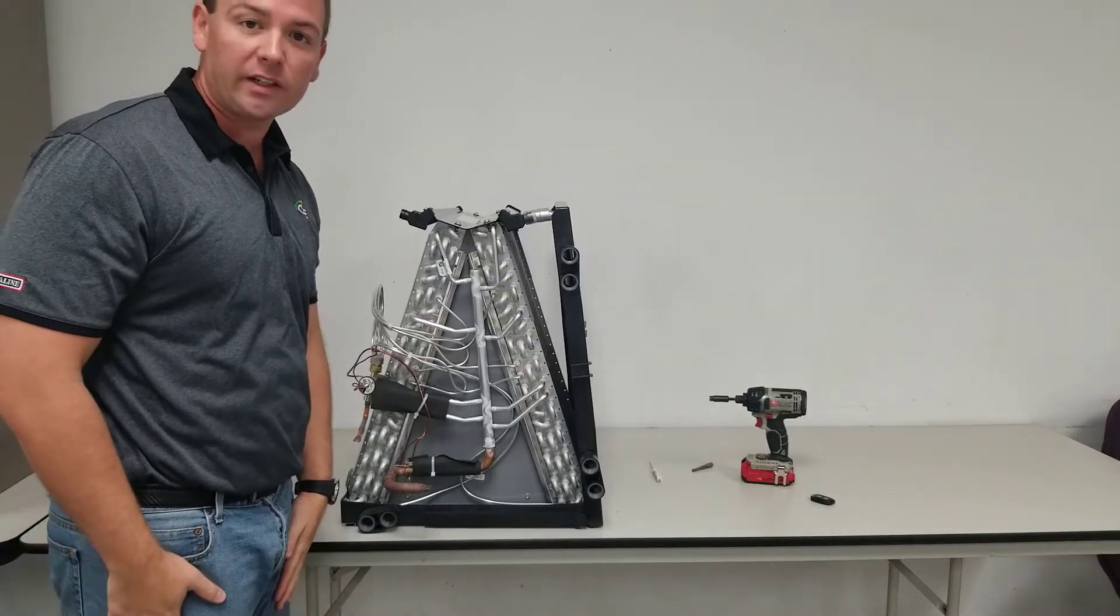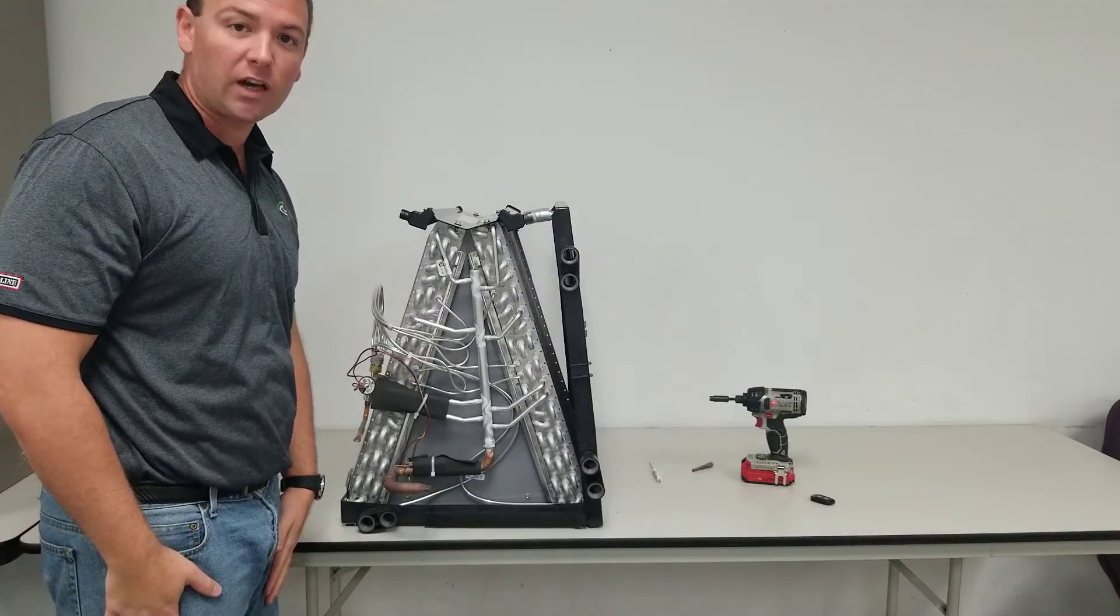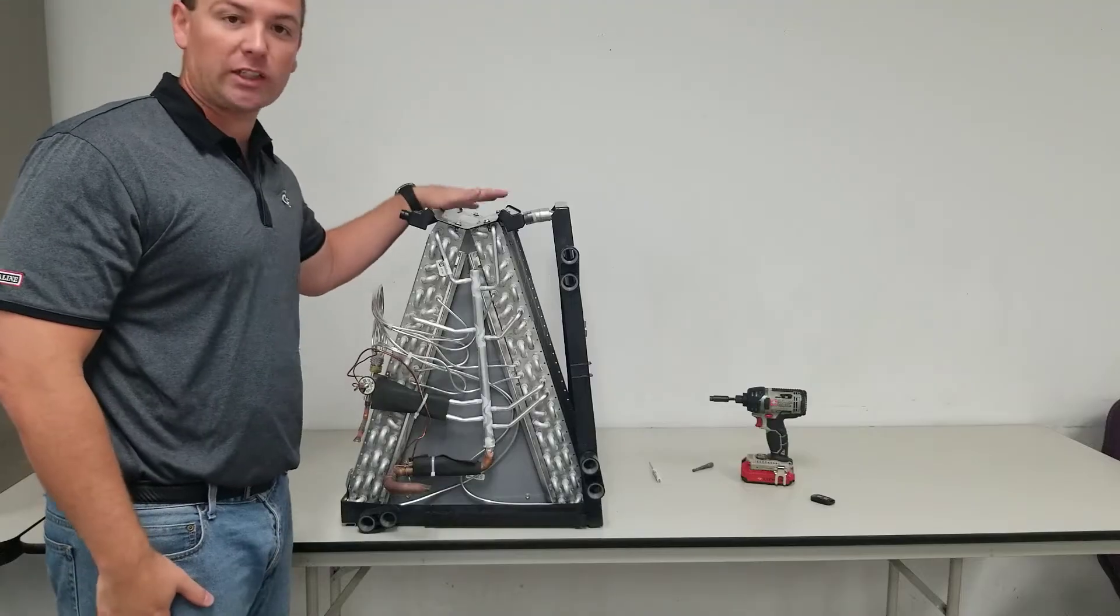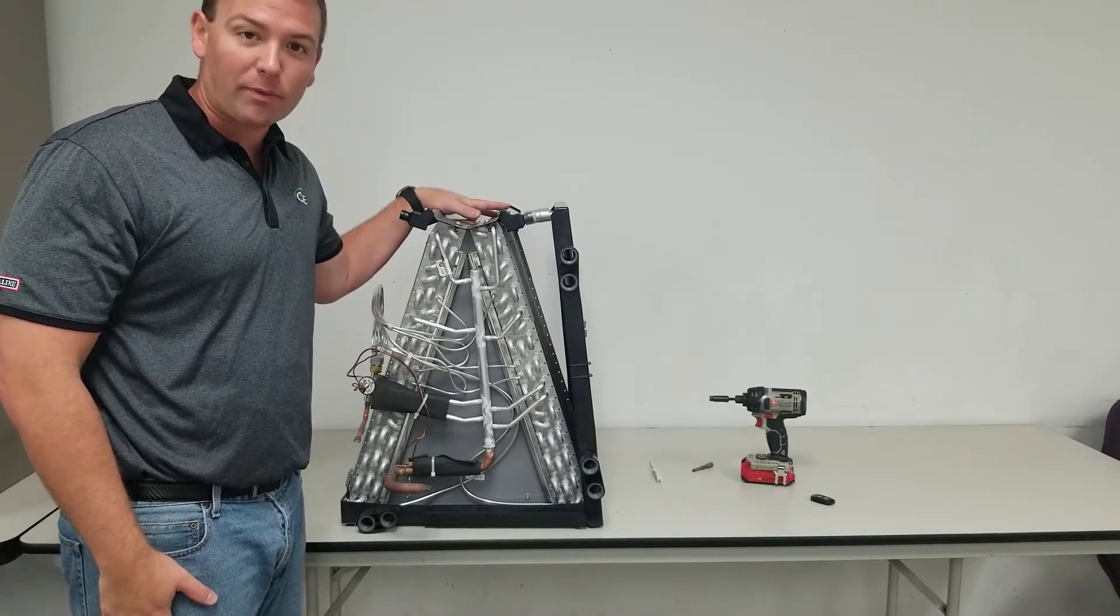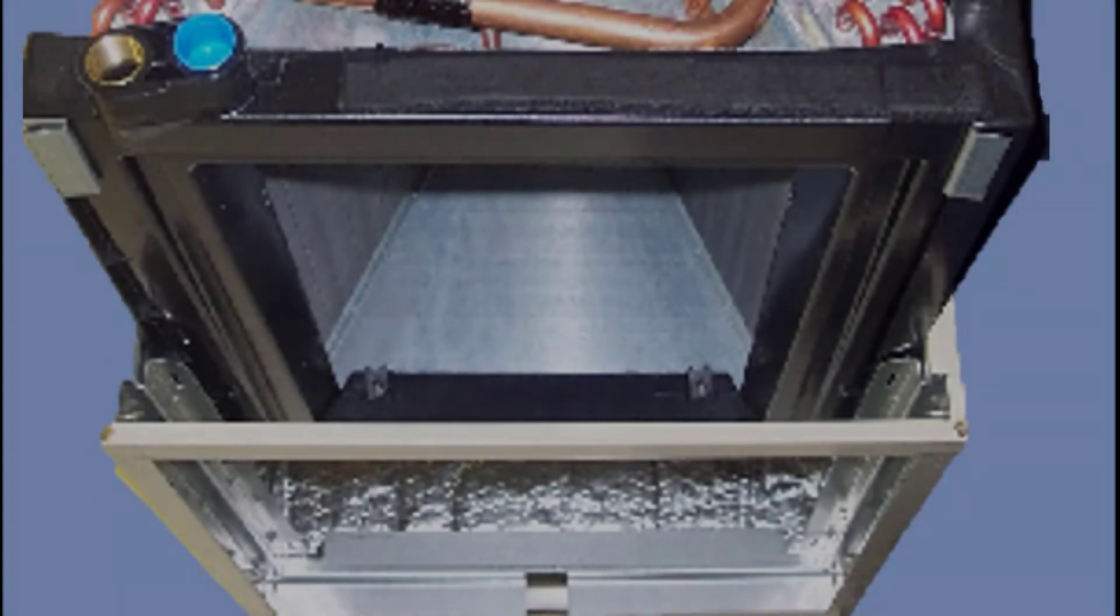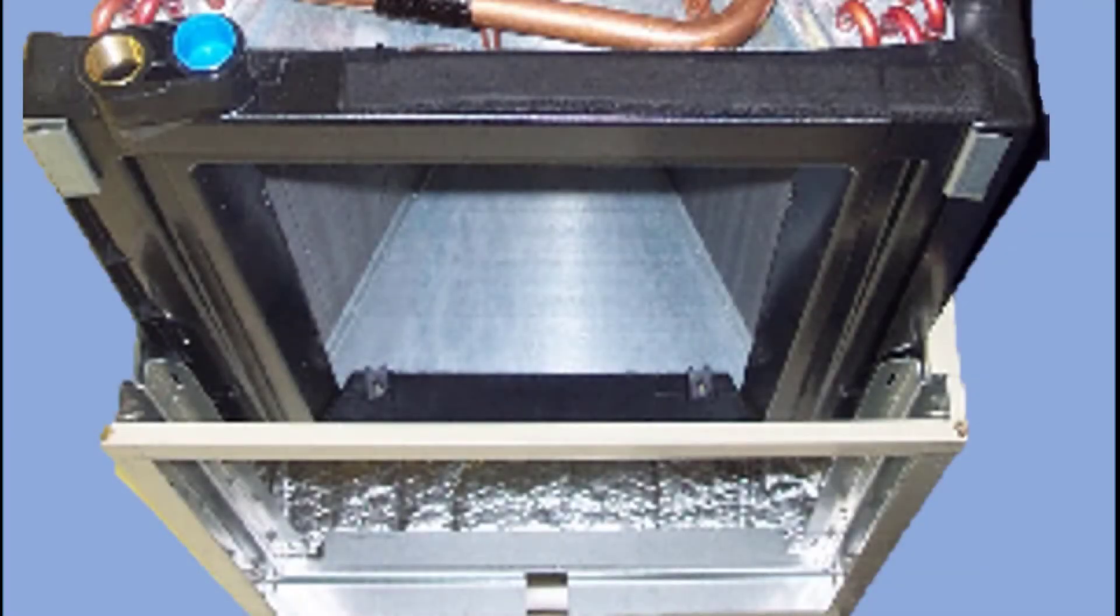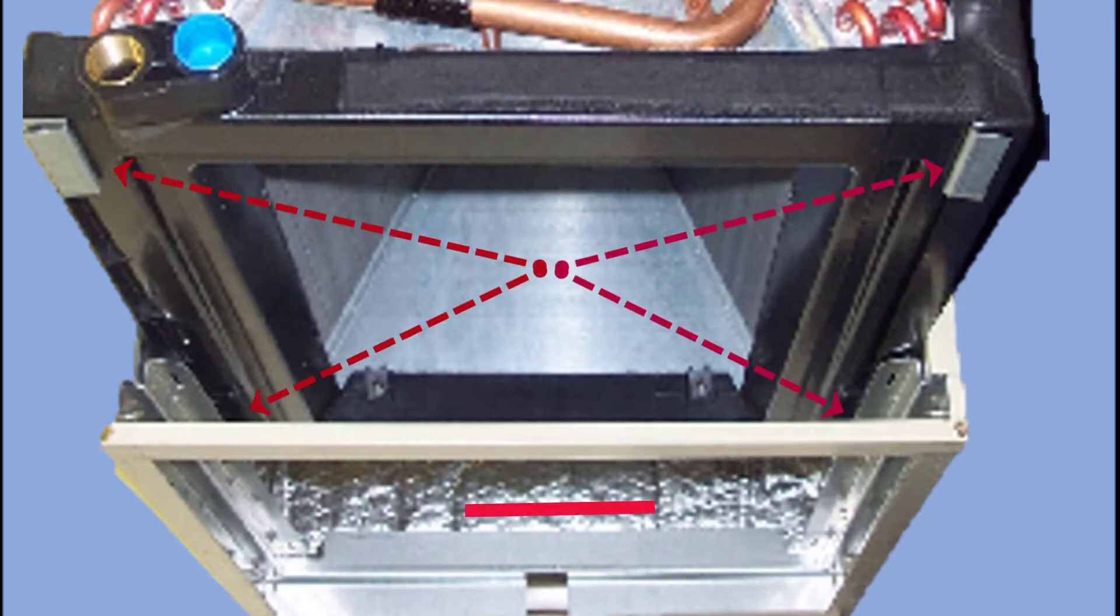You've just completed the right hand conversion of the coil. It can be reinstalled in the air handler and then installed in a horizontal right application. When you slide the coil assembly back into the fan coil, please make sure the four coil support brackets properly engage the coil support rails on the right and left side of the unit. This is a very important step, but even more important in a horizontal application.